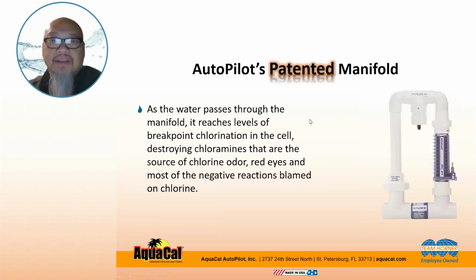The patented manifold assembly, like I mentioned before, has a check valve on the bottom that allows us to regulate the flow going through the top. This is how it comes from the factory: the flow comes in, and that spring check valve opens and closes based on the amount of flow going through there. There's a screen right in there so we can trap any debris before it gets up into the sensor, which is located at the top.